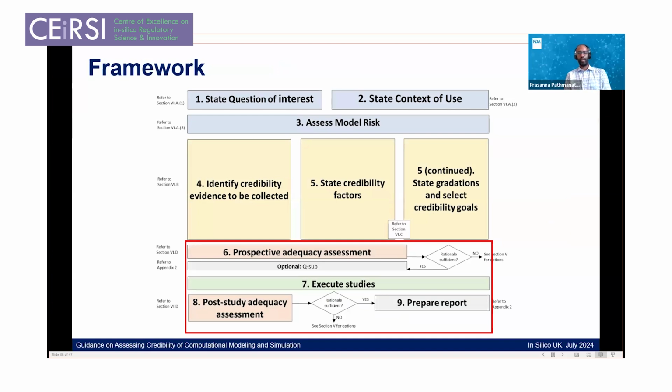And at that point, we recommend coming in with something called a Q submission, which is a mechanism to obtain feedback from CDRH, the device center, on any regulatory question about a medical device. So the recommendation is to provide a Q sub saying: this is what the intended use and indications for use of the device are.